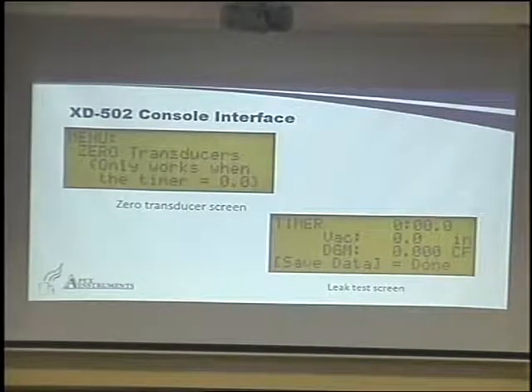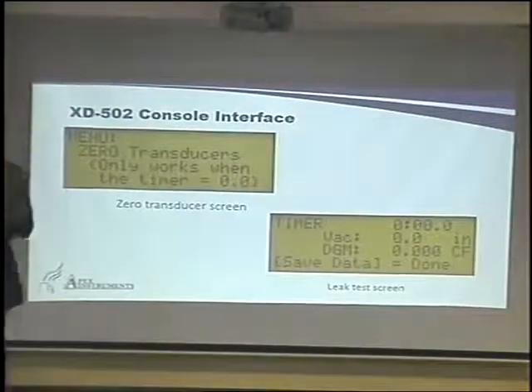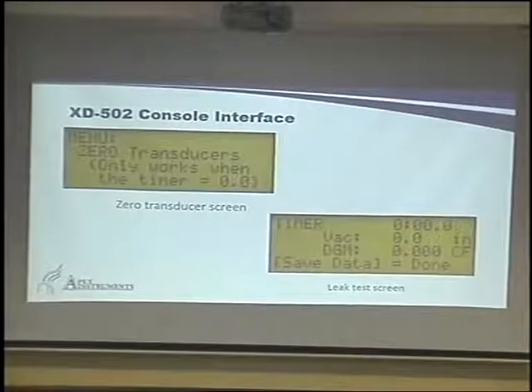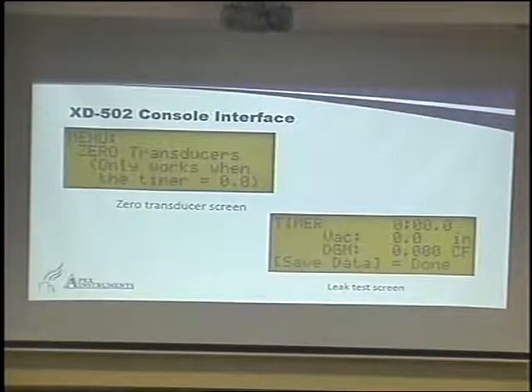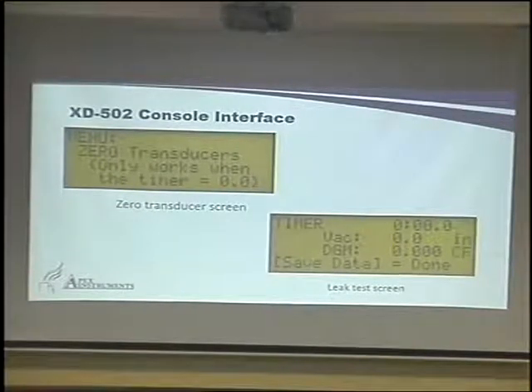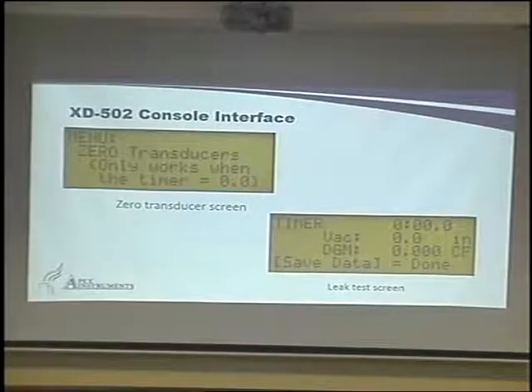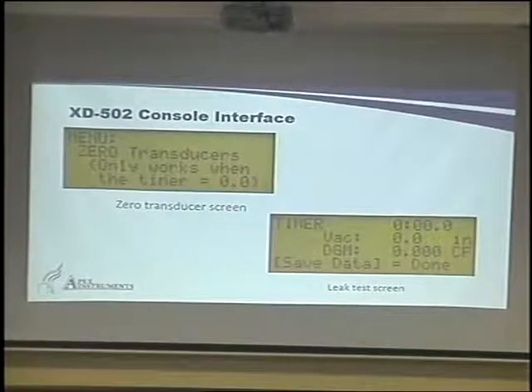on the instrument. And you can see there's a note here. This only works when the timer is at zero. So if you're operating the instrument and the timer is running, so you're recording how much sample time you're using, you can't accidentally zero your transducers, which would be catastrophic to the test. It would make all the information irrelevant. So it's kind of like a safety feature, that there's certain things you can and cannot do in the instrument, provided that other things are not working. You know, when the timer's running, the instrument thinks that you're in the middle of a test, so you can't change certain things because it's not allowed by the method, or it would completely destroy all the data that you're collecting.